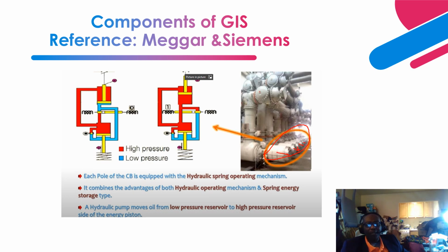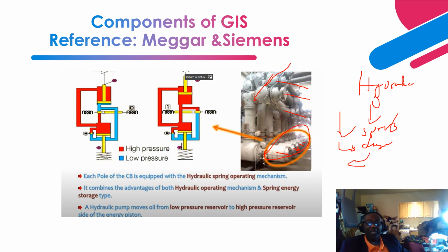So as you can see, the number of circuit breakers that each hydraulic operating mechanism is integrated to. Okay, so this is the horizontal basis. As you can see over here, the disconnect switch is also shown. Basically this one is utilizing a hydraulic system, utilizing pressurized oil, and that is integrated to a spring system. The spring system is compressed and charged. Once it is charged and compressed, it is integrated to the mechanical linkage of the circuit breaker. The linkages are interconnected and basically operate the breaker to an open or closed position.